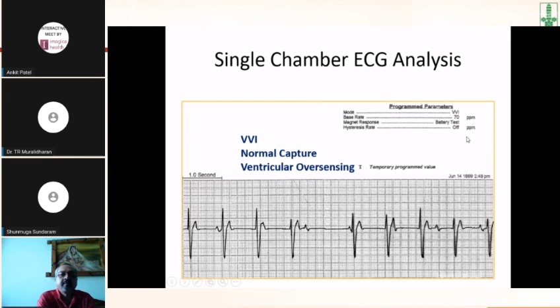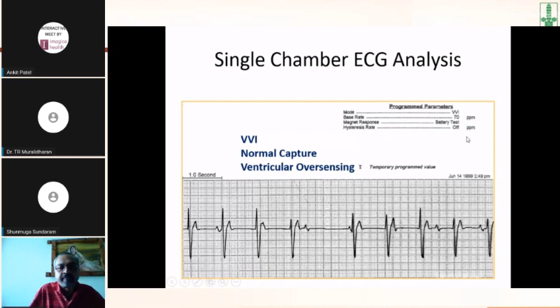So, sorry, oversensing. Normal capture in the third beat, fourth beat is fine, fifth complex, it senses something and has not delivered. There's a small pause before the sinus beat occurs. So we have to run through each and every complex, see if it is sensed or paced, whether the pacing stimulus artifact occurs on time, whether it has sensed something, oversensed or undersensed. The best way to diagnose oversensing is when the pacing spike falls all over the QRS complex. Next.